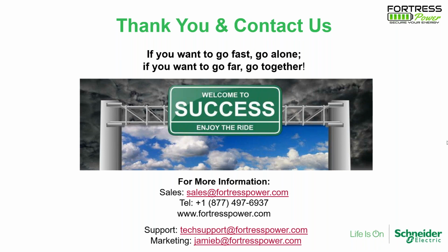Will the battery work in temperatures in Puerto Rico of 105 degrees Fahrenheit? If it's not under the sun directly, with certain ventilation in an indoor situation, it's usually fine. With communication with Schneider, we don't see the problem, so the BMS will regulate the production of the battery too. That's one of the beauties of having a closed loop communication, it's just a big plus for the longevity of the batteries.